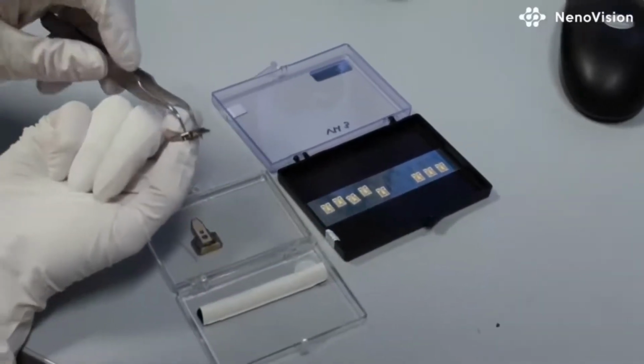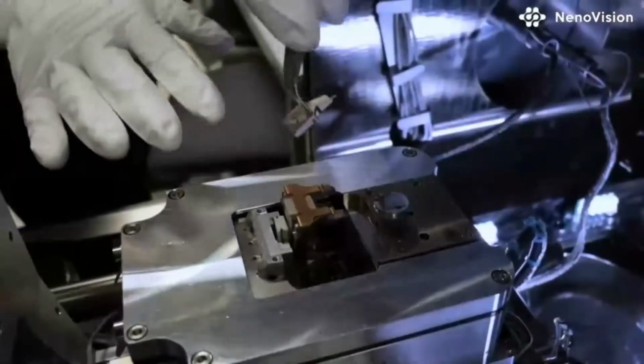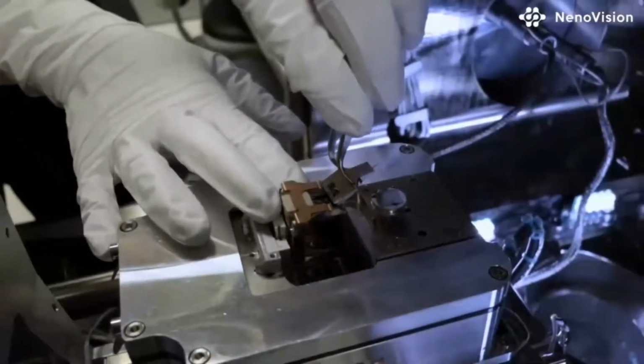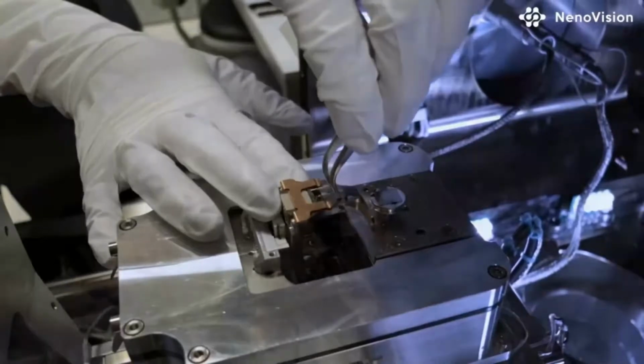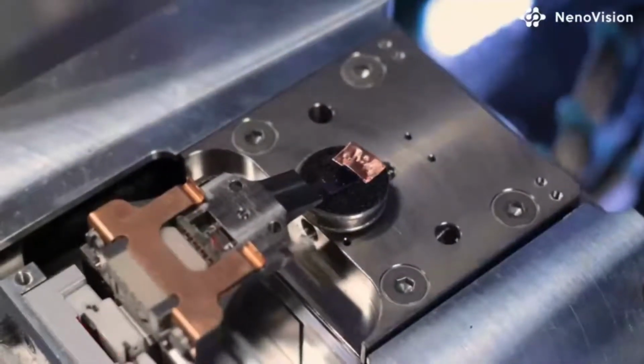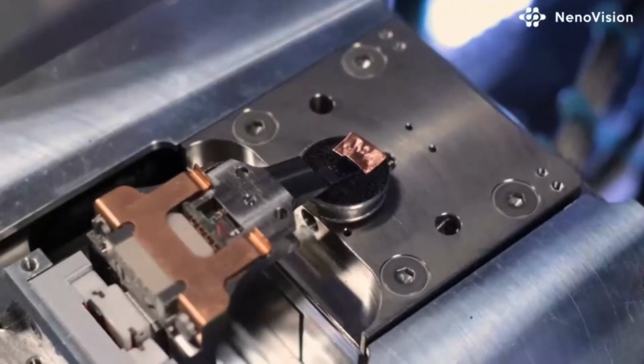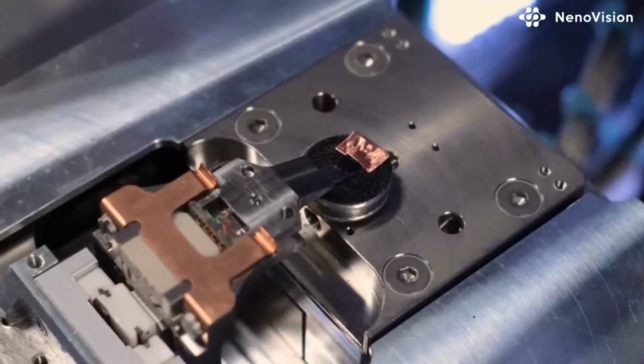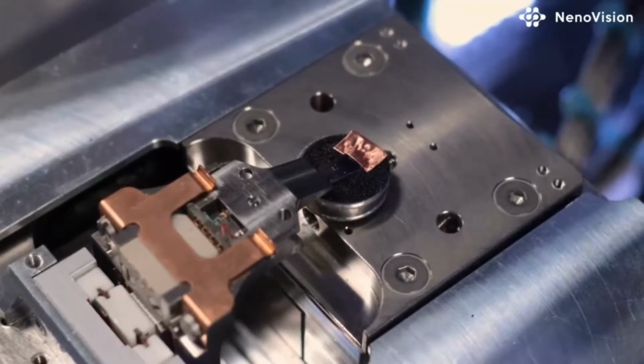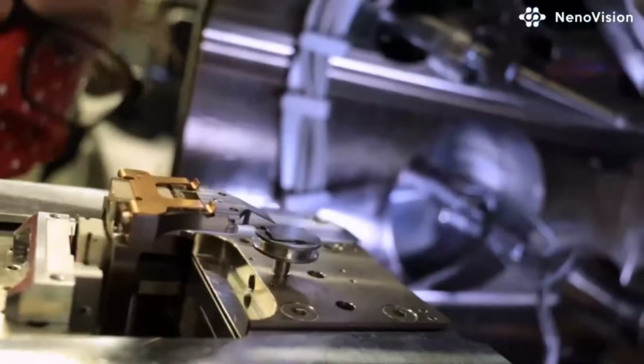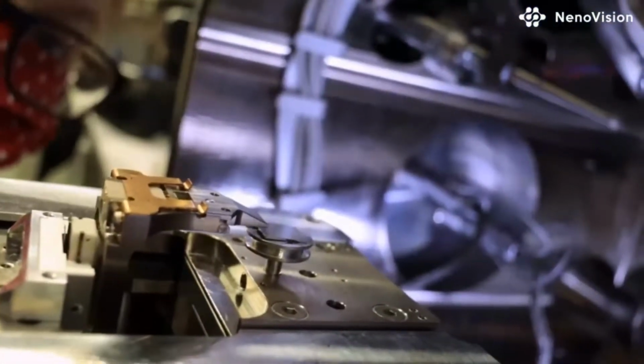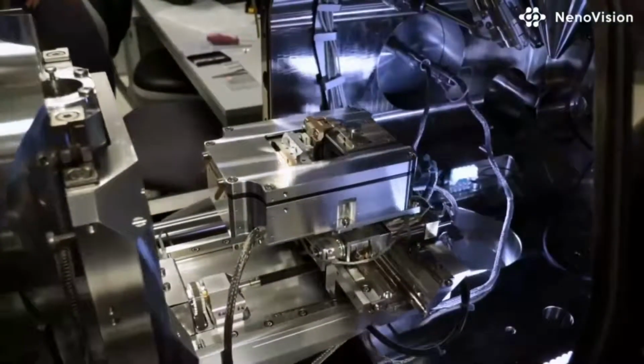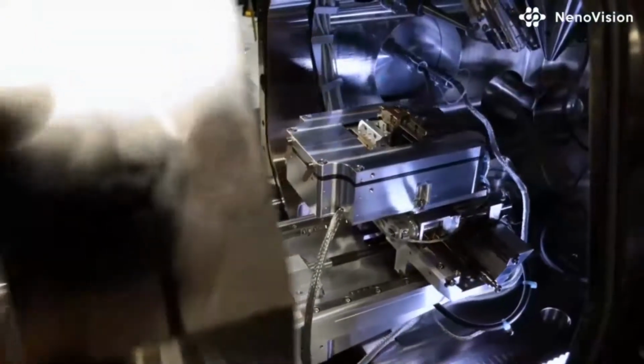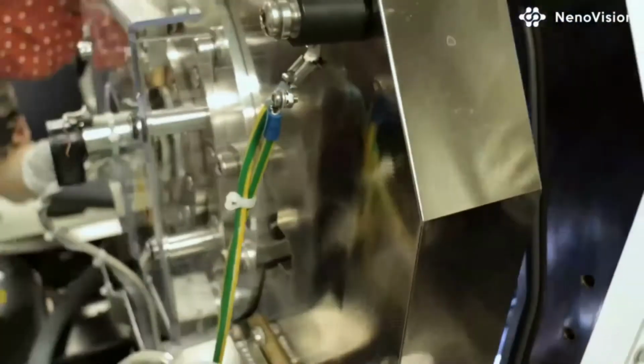As you can see, there is enough space between the sample and the probe, so these steps can actually be mixed up. Finally, we roughly move the probe tip to the area of interest by eye, and even finer in that direction. I will talk about the probe movement later as we start working in the NanoView software. Now we can close the door and double check the cables.